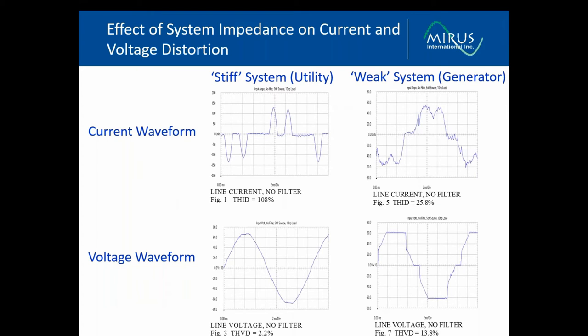Although current distortion decreases on higher impedance weak systems such as generators, it does so at the expense of voltage distortion. So here we're showing the application of a variable speed drive on a stiff system, a low impedance utility source. Here the drive is not equipped with an AC line reactor or DC link choke, and it draws current at 100% distortion. You see very sharp pulses which contain a lot of harmonic content. But if we look at the voltage distortion on this utility feed, it is only 2.2%. So even though there's a lot of current distortion, there's very little voltage distortion.